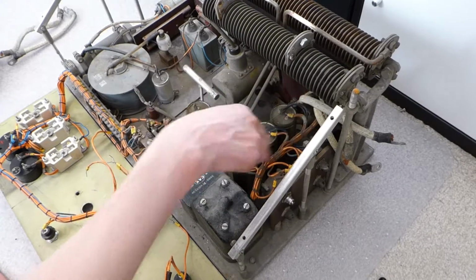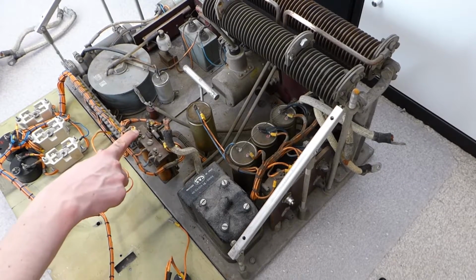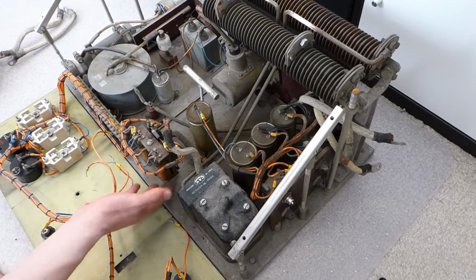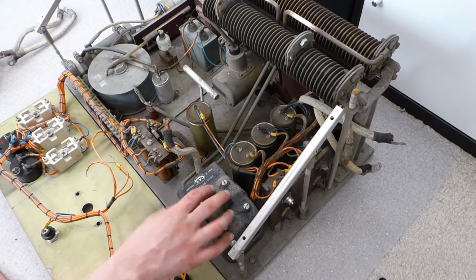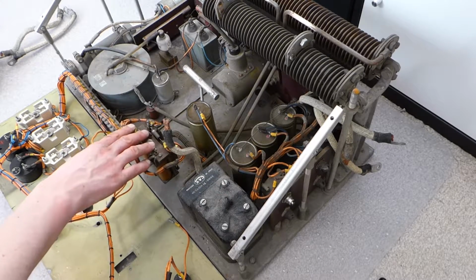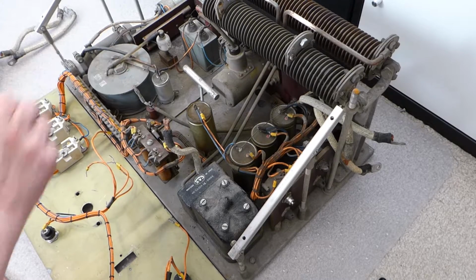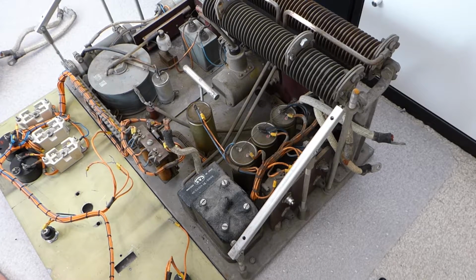All of these timing capacitors go into those 2 relays down here. One of the relays controls this contactor here, and the other relay controls that contactor on the back that's responsible for turning on the high voltage generator.